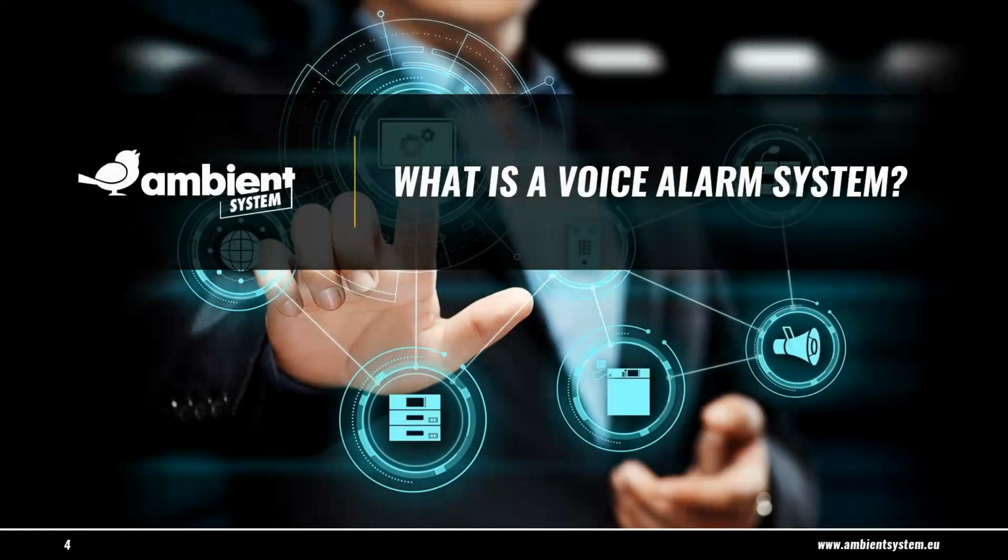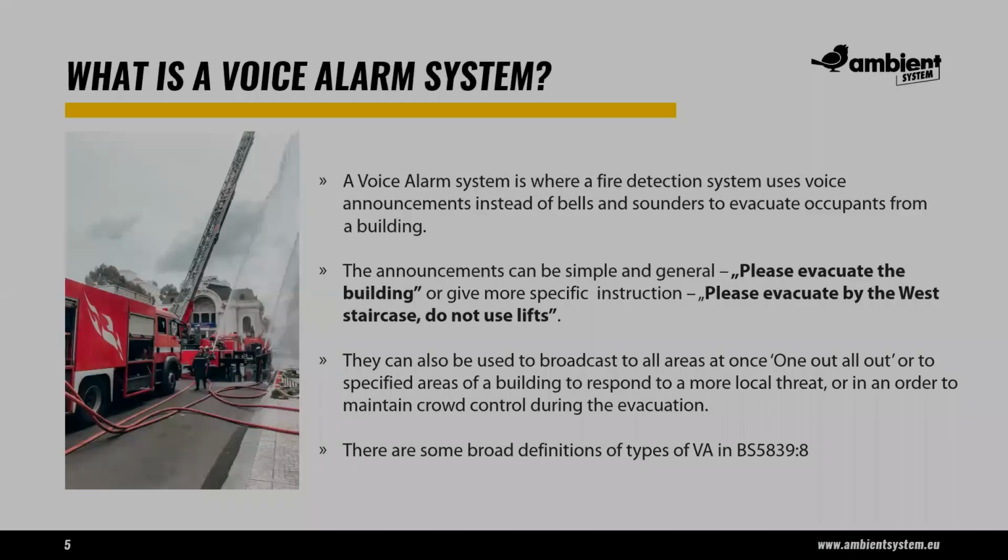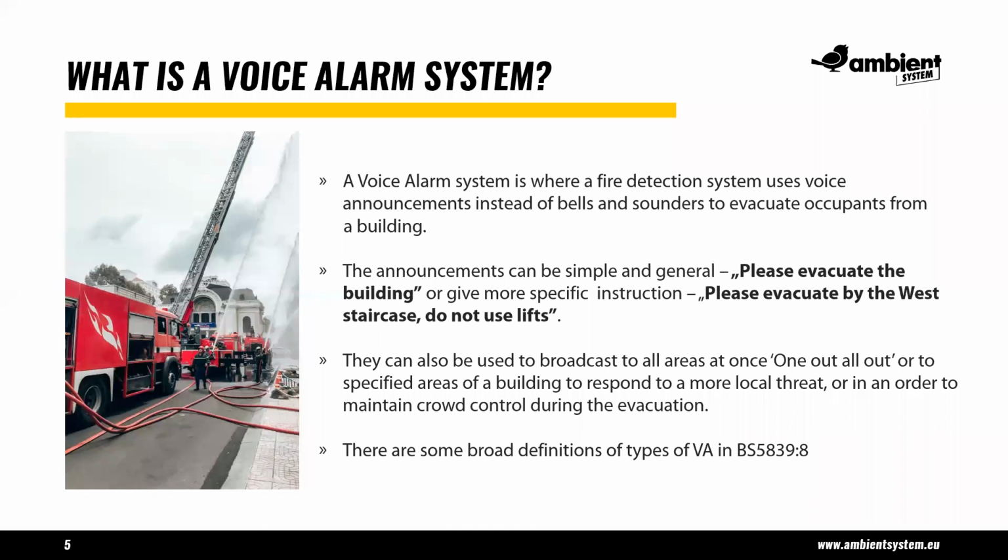So this voice alarm system business, what really is a voice alarm system? As we've mentioned, the idea is that the fire detection system, which is a selection of detectors, break glasses, smoke detectors, heat detectors, connected to a fire panel, instead of them being connected onto bells, uses voice announcements to give evacuation instruction to occupants out of that building. And the point of these announcements is that they can be specific. They can be simple, so please evacuate, or they can say, please evacuate by the west stairs, do not use the lifts, or do not use the east stairs. And you can basically pilot people away from danger. That's the purpose.